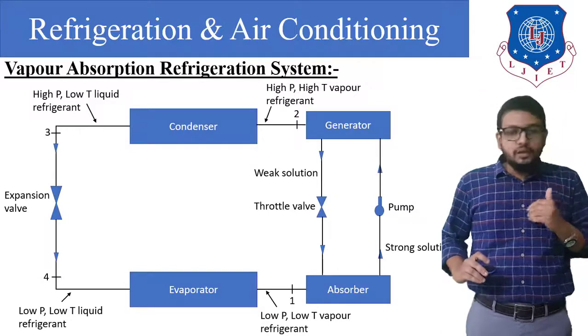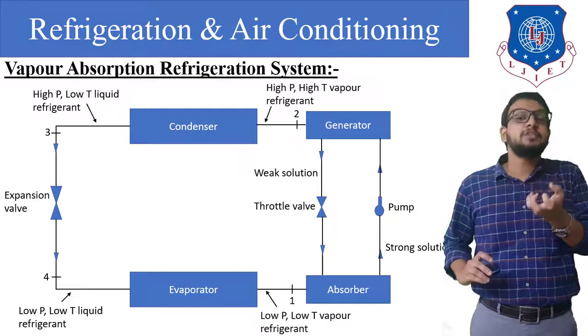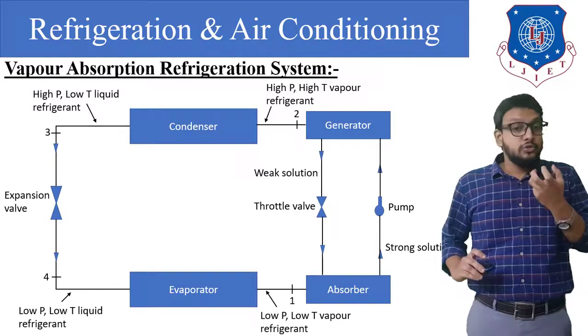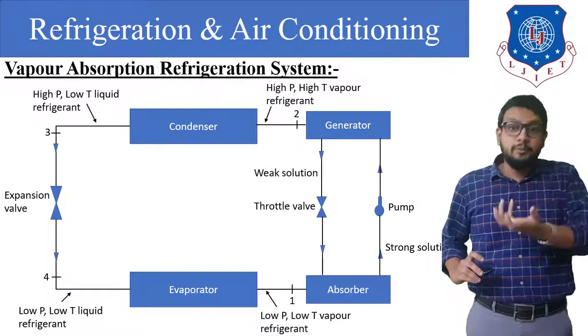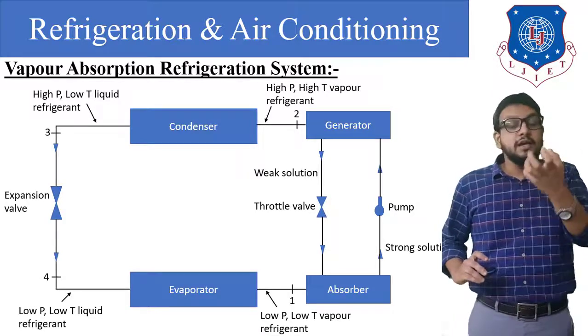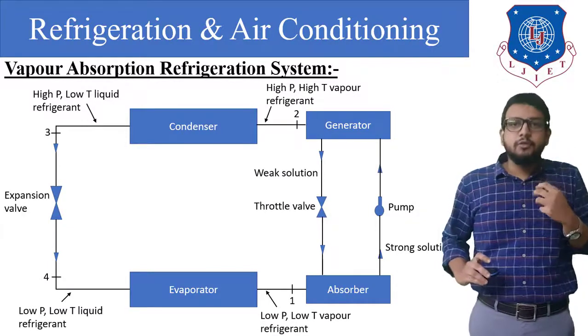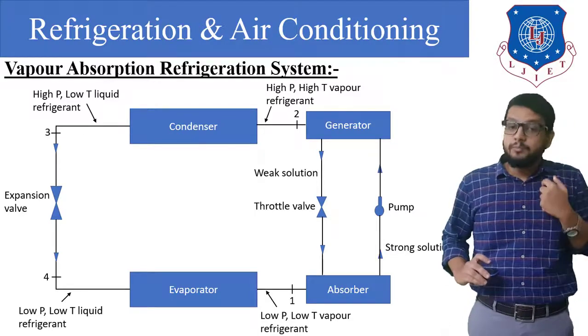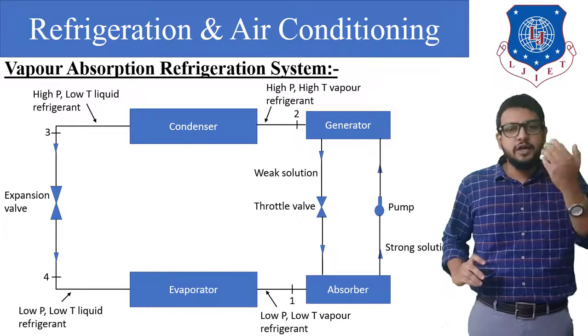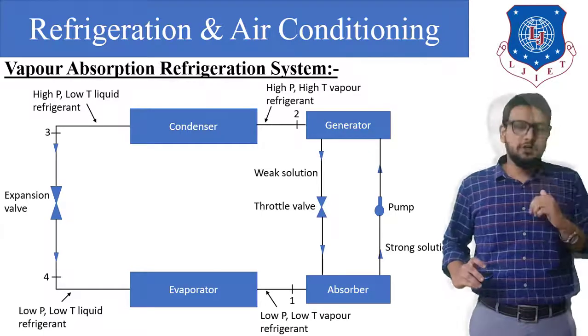The function of the three known components: the evaporator is placed in the freezing compartment where cooling effect is required — it converts liquid refrigerant into vapor by absorbing latent heat. The condenser is placed at surrounding temperature, so heat transfer takes place from vapor refrigerant to the atmosphere. The expansion device reduces the high pressure of the refrigerant at the condenser exit down to the low pressure required by the evaporator.